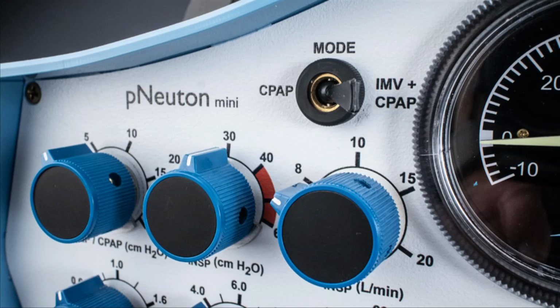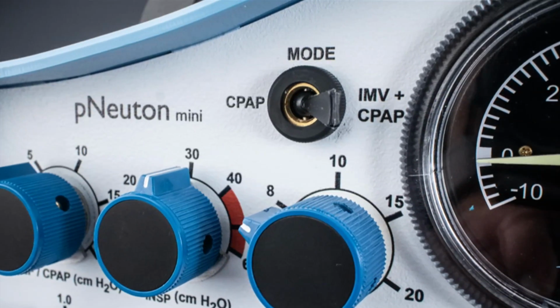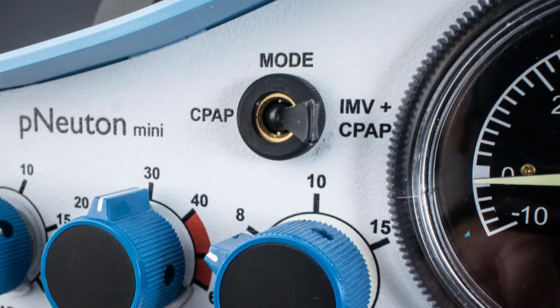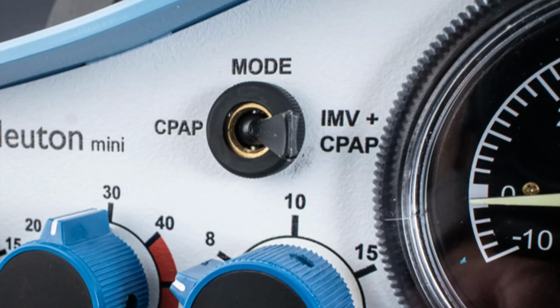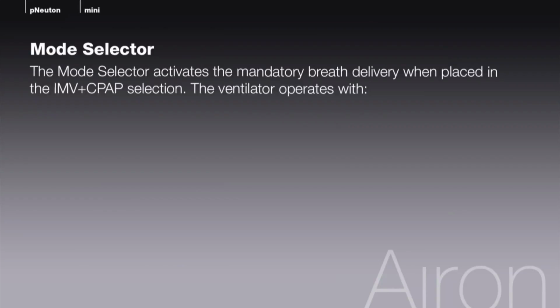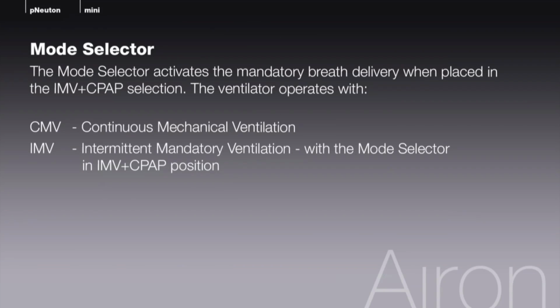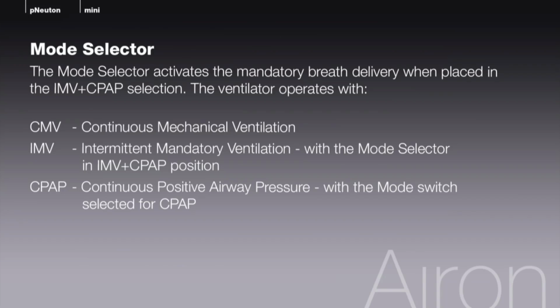Mode selector. The mode selector toggle switch activates the mandatory breath delivery when placed in the IMV plus CPAP selection. The ventilator operates with CMV, continuous mechanical ventilation, IMV, intermittent mandatory ventilation, with the mode selector in IMV plus CPAP position, and CPAP, continuous positive airway pressure, with the mode switch selected for CPAP.